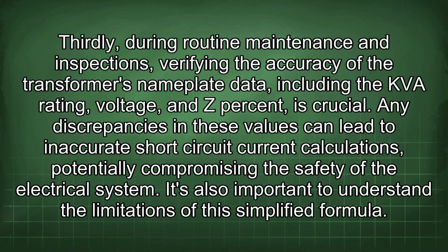Thirdly, during routine maintenance and inspections. Verifying the accuracy of the transformer's nameplate data, including the kVA rating, voltage, and Z%, is crucial.